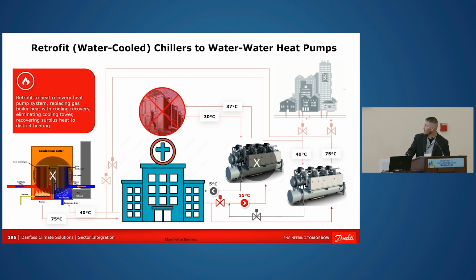So we've taken out the chillers, taken out one of the heat pumps for that, and added that into the full system, and gotten rid of your plant, your boilers, and utilizing the hospital as a base load for the heat pumps for the rest of the system.